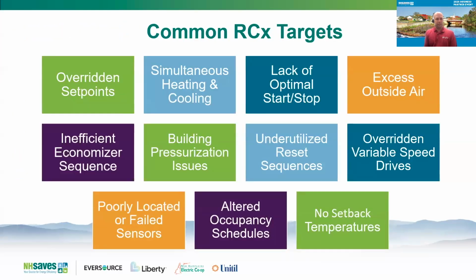Common retrocommissioning targets. These aren't necessarily sequences. They're more issues that you'd be looking for. So simultaneous heating and cooling, one of my favorites. You've got a VAV air handler providing 55 degrees all day long, 365, and it'll work just fine because the downstream reheats will just reheat the air whenever the space is getting overcooled. But it's massively energy inefficient. Putting in a nice supply air temperature reset sequence, ideally based on heating and cooling demand, is ideal, and not just looking at broad-stroke outside air resets, but really driving to the load and what impacts that sequence is really important.